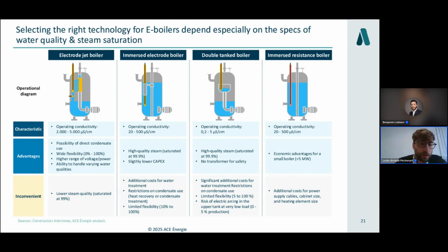What you have to know is that each boiler has different characteristics. For example, regarding conductivity inside the boiler: jet boilers allow running at high conductivity, immersed boilers work at low conductivity, and double tank boilers work at very low conductivity.